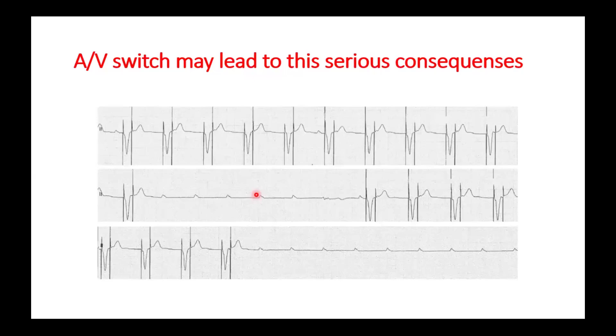Then you have to go to the cath lab, open the wound and change the lead. The atrial lead should be in the atrial port and the ventricular lead should go back to its own port. I found this twice in my life and I did it once, but I discovered it inside the cath lab. Another solution is to place a magnet. If you don't have a programmer available, just place a magnet immediately, of course.